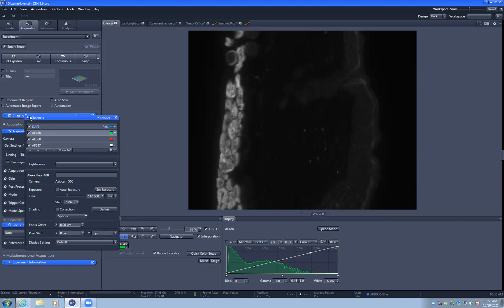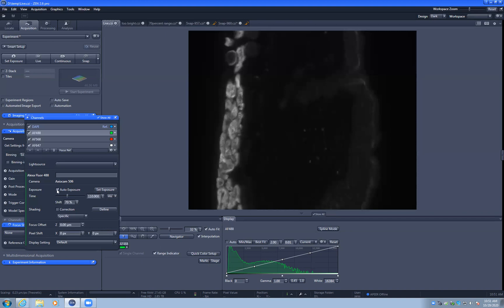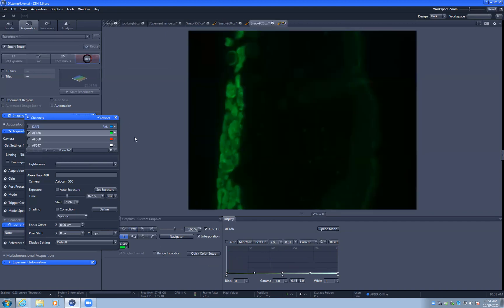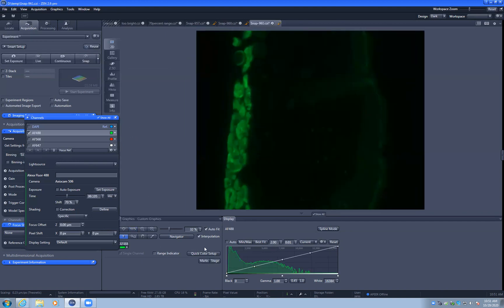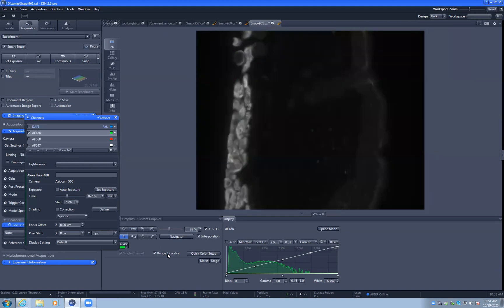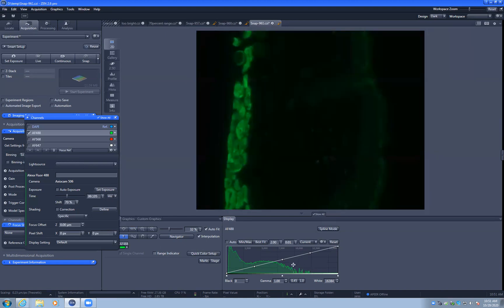Now, there's a way that this software can automatically calculate the exposure time for you, and leave some padding for some error when you go to another part of the field. So here we have where it says shift to 70%. What this means is that it will aim to have the brightest pixel in your image at 70% of the full range. So we have 16,384, so it's going to go to approximately here, and say this is going to be our brightest pixel. So if we say 70% auto exposure, set exposure, it took a picture. Now if I hit snap with all the other channels turned off, and you can see that there's no saturation. You can see on this curve that it's peaking at approximately 70%.